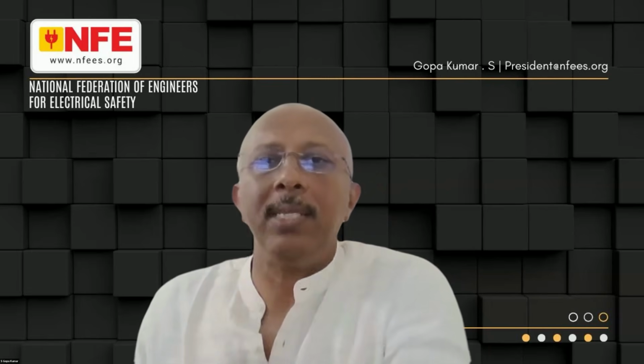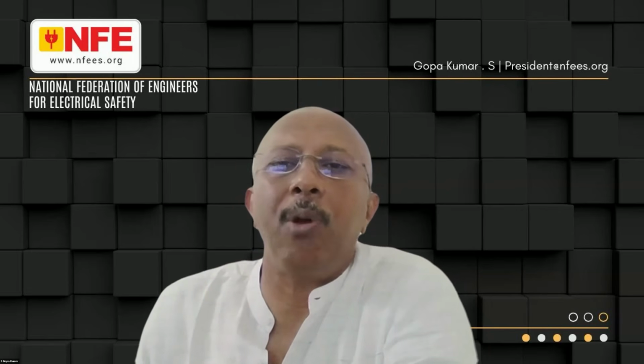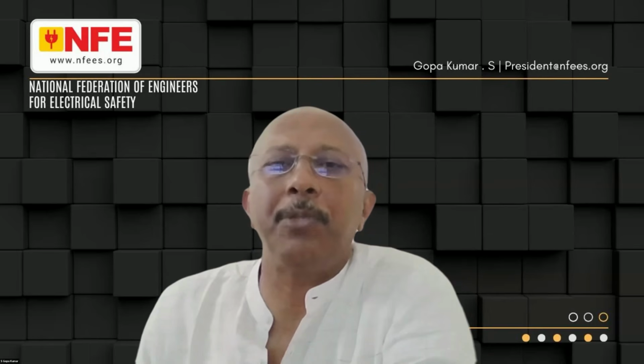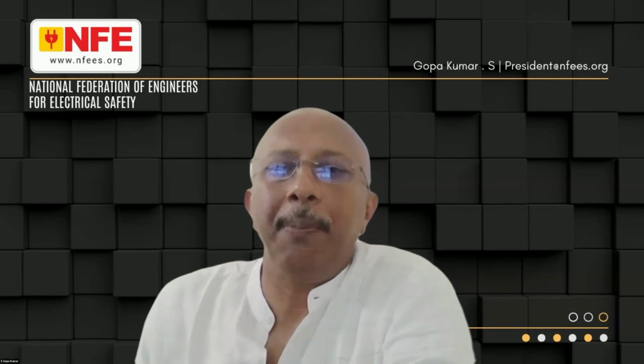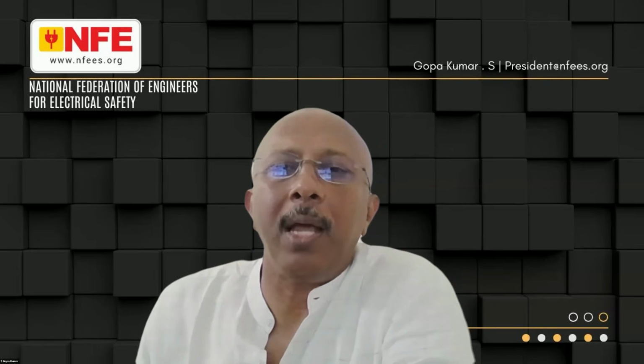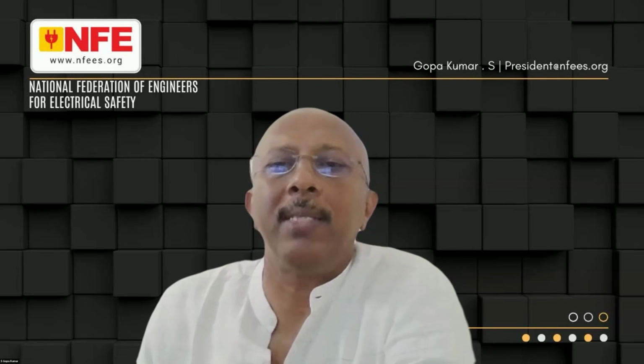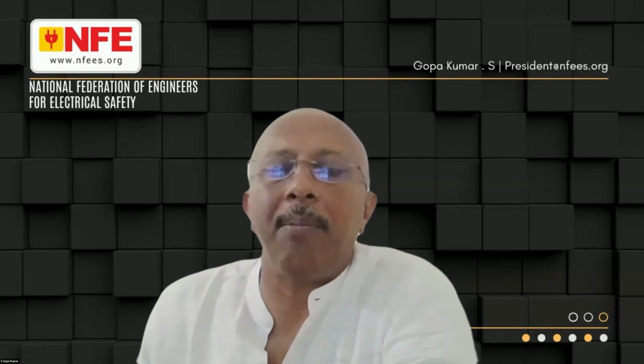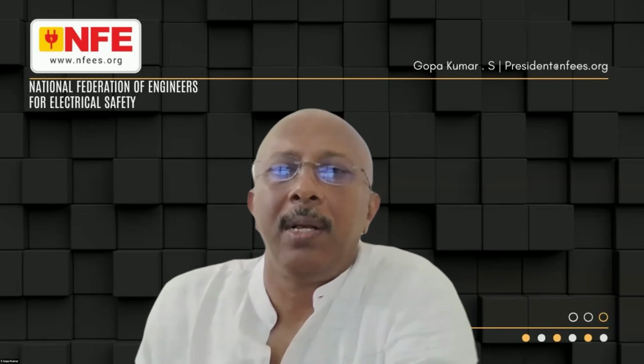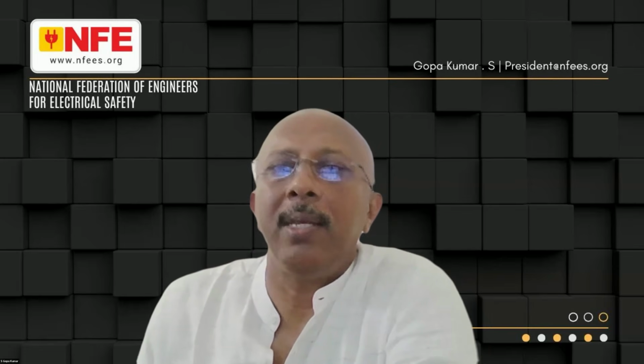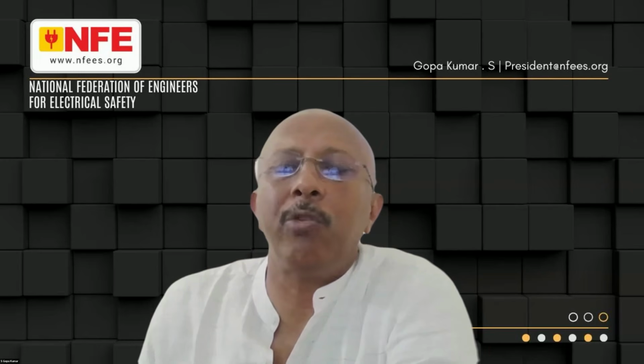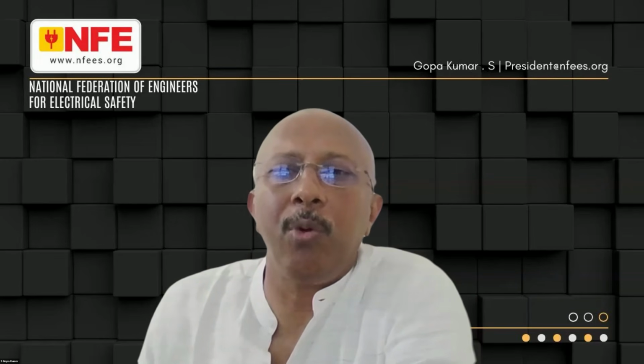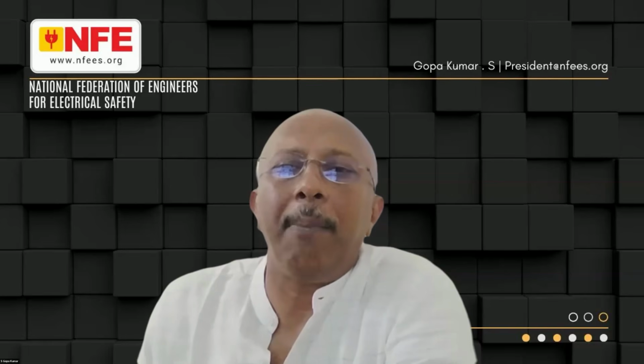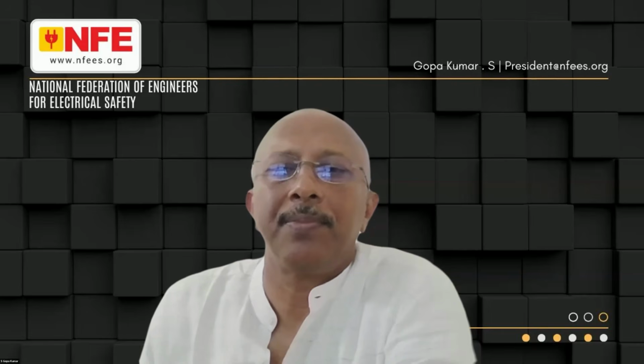Mr. Fernandez, I understand from your presentation, a separate earth pit is not required for biomedical equipment. Absolutely, you are correct. A separate earth pit for biomedical equipment is absolutely not required. If any biomedical equipment supplier is demanding it, as I said, they are making a mistake. So please don't provide it. Look into the technical specification. Mostly, if the equipment is imported equipment, look at the original manual. The subject is very much included in the manual.